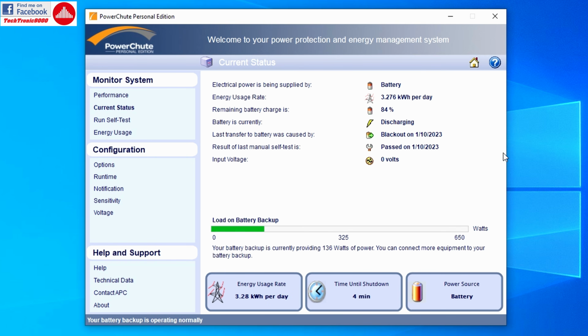The battery is discharging here, 84%. This is somehow pre-programmed into the UPS logic, so it doesn't know I'm actually using a bigger battery, but it will run longer. If it says 2 minutes here, it's probably going to be 4 minutes. If it's 4 minutes here, it's probably going to be 8 minutes. We don't care about that time to shut down too much.